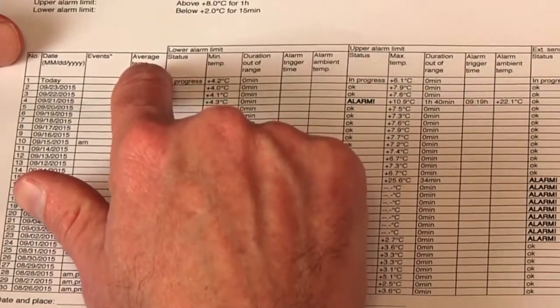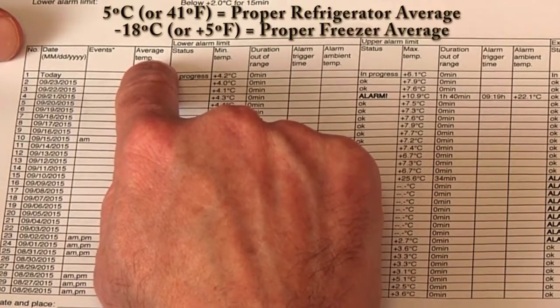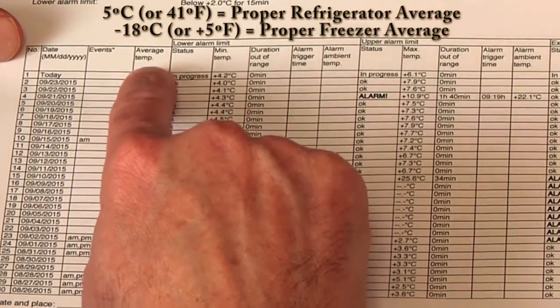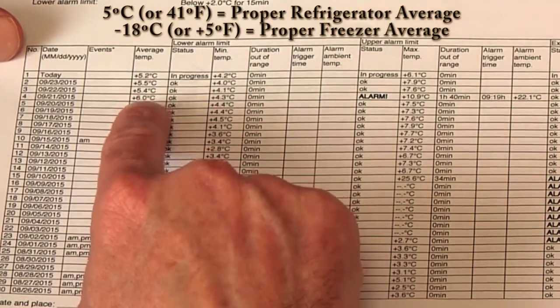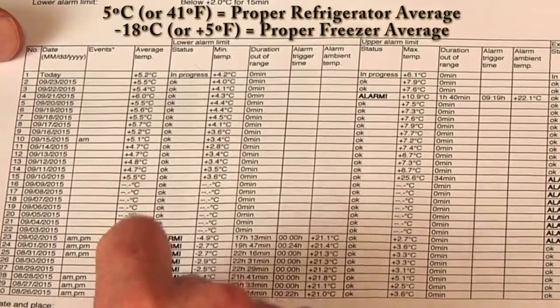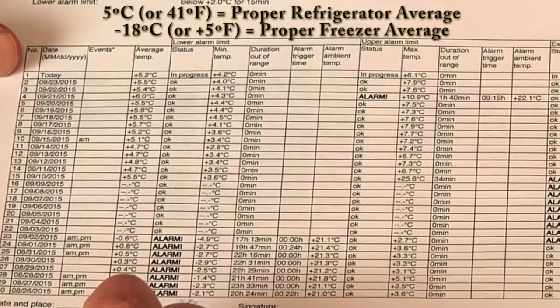This column here is an important column, average temperatures of your storage unit. In a refrigerator unit, that should be 5 degrees C or 41 degrees Fahrenheit.